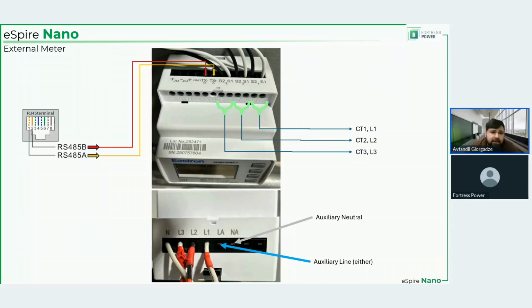Ports number 17 and 18 are going to be for CT2, which monitors L2. And CT3 will be 15 and 16 for L3. And again, these L1, L2, and L3 must coincide with the reference cables that you have shown in the bottom.